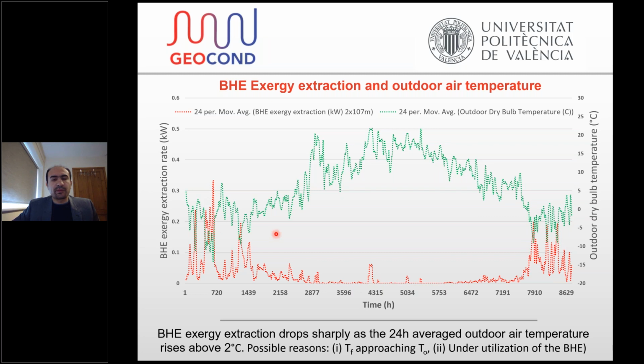So the exergy efficiency is around 25%, because it could improve if there's more variation between the thermal energy extracted from the BHE and what we're supplying — if there's a greater difference between the outdoor air temperature and the temperature of the energy flow supplied to the building or extracted from the BHE.